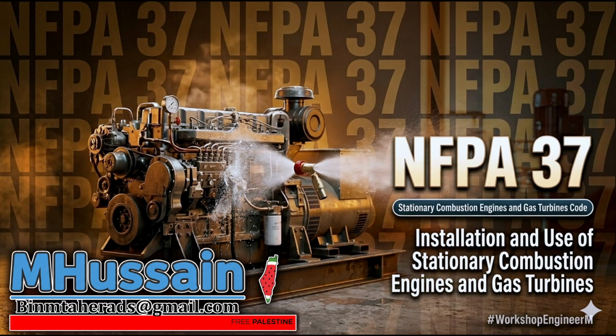So to really get the philosophy of NFPA 37, we kind of have to compare it to another code everyone knows, right? NFPA 110. Yeah, NFPA 110 is the standard for emergency and standby power systems, but their goals are completely different. How so? Like, what's the fundamental difference there? Well, NFPA 110 is entirely focused on electrical reliability. It asks, when the grid goes down, does the engine start? Does the transfer switch work? So it's basically making sure the lights actually come on. Exactly. It's an operational mandate. It assumes the grid will fail, and its job is to guarantee the engine runs.